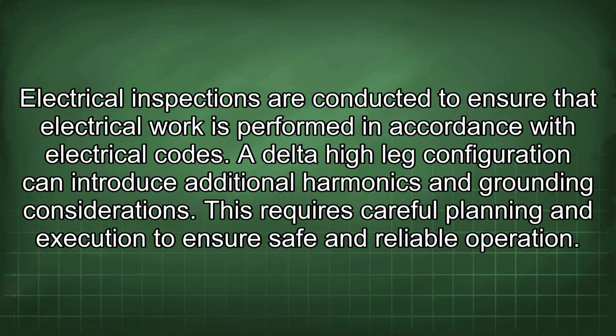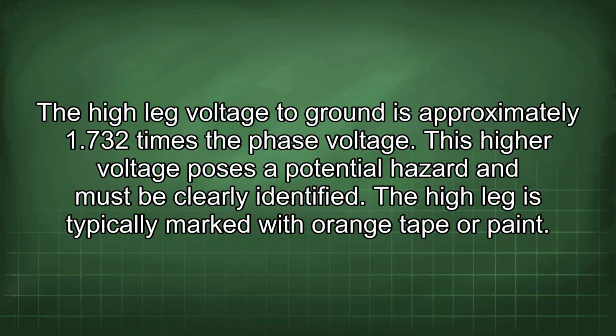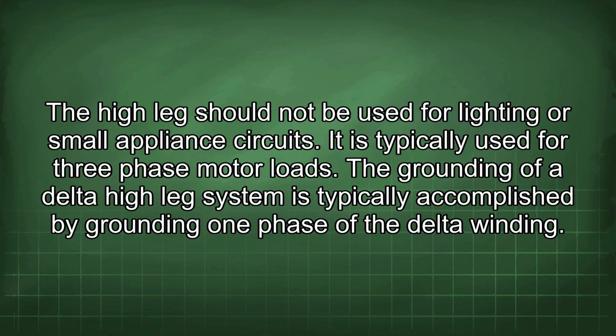A delta high leg configuration can introduce additional harmonics and grounding considerations. This requires careful planning and execution to ensure safe and reliable operation. The high leg voltage to ground is approximately 1.732 times the phase voltage. This higher voltage poses a potential hazard and must be clearly identified. The high leg is typically marked with orange tape or paint. The high leg should not be used for lighting or small appliance circuits. It is typically used for three-phase motor loads.